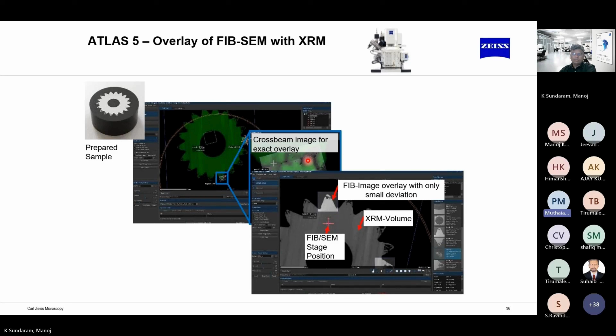This is another example of the correlative. We identify a defect in an XRM, and on the FIB-SEM, we do the material removal and the imaging. Post imaging, the right-hand side bottom image is the SEM image, and on the left-hand side, the 4 colored images are the chemical composition, or chemical mapping, of the contaminant, where you can see iron, manganese, chromium, and copper present in the aluminum printed part.